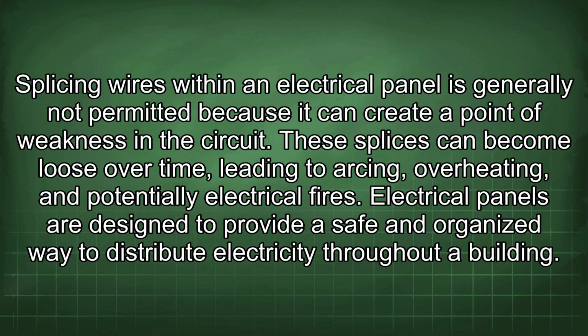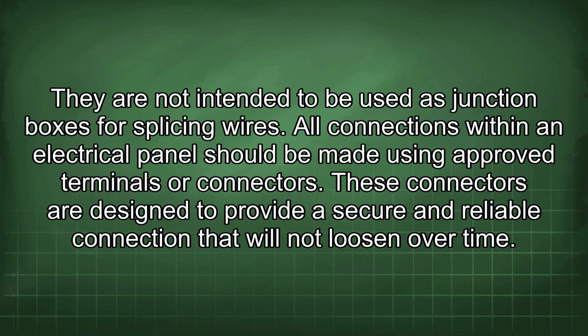Splicing wires within an electrical panel is generally not permitted because it can create a point of weakness in the circuit. These splices can become loose over time, leading to arcing, overheating, and potentially electrical fires. Electrical panels are designed to provide a safe and organized way to distribute electricity throughout a building. They are not intended to be used as junction boxes for splicing wires.